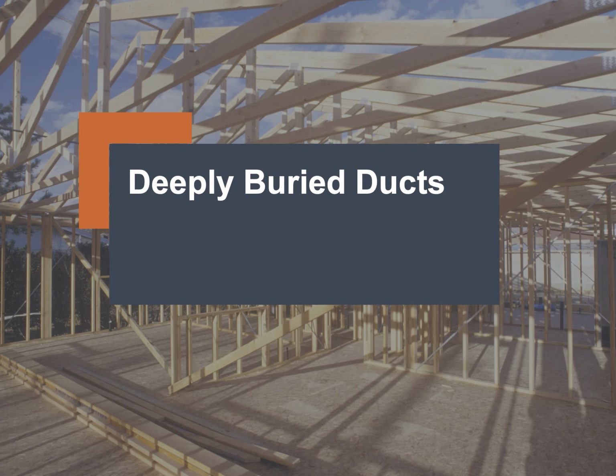For Oregon builders, the Oregon Residential Specialty Code requires that ducts be installed inside the conditioned space. But there's an exception in the code which allows them to be sealed and buried in a deep layer of attic insulation. In Washington, builders can earn code credits for these deeply buried ducts. No matter where you build, you might want to try this approach as you transition towards ducts inside. You could start the process by moving the air handler inside and then use the deeply buried ducts approach until you're ready to modify your standard designs to accommodate the ductwork to be fully within the conditioned envelope.